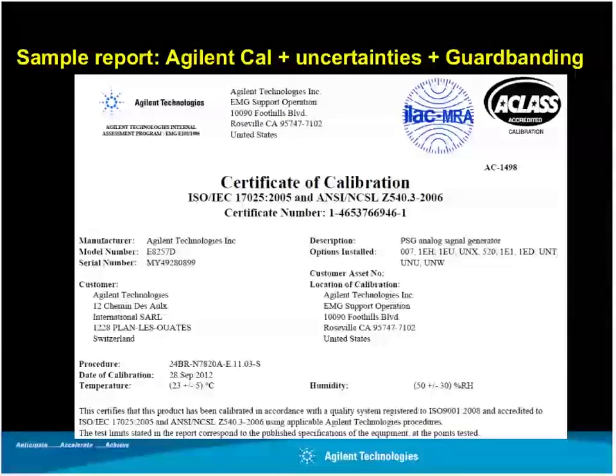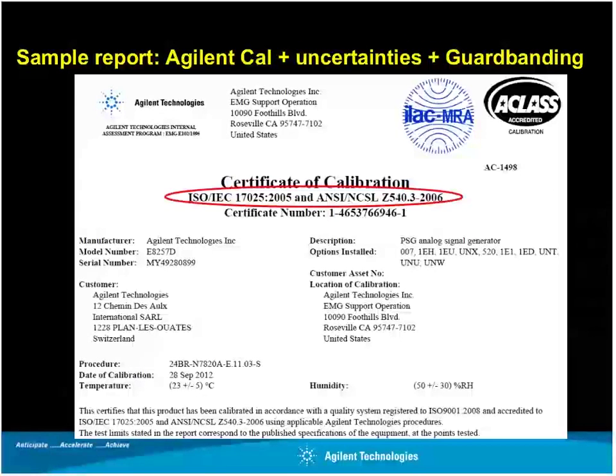So when you receive a calibration report, for example, this sample report from one of our calibration services, which would be the Agilent calibration with uncertainties and also with guard banding according to ILAC G8, then in that case, this is coming from a U.S. laboratory, this particular example. So it has the ACLASS one. If it were coming from, say, the UK, then it would have the UKAS one, of course.